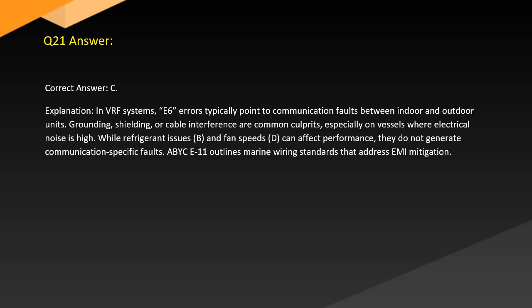Answer. Correct answer: C. Explanation: In VRF systems, these errors typically point to communication faults between indoor and outdoor units. Grounding, shielding, or cable interference are common culprits, especially on vessels where electrical noise is high, while refrigerant issues (B) and fan speeds (D) can affect performance. They do not generate communication-specific faults. ABYC E-11 outlines marine wiring standards that address this.